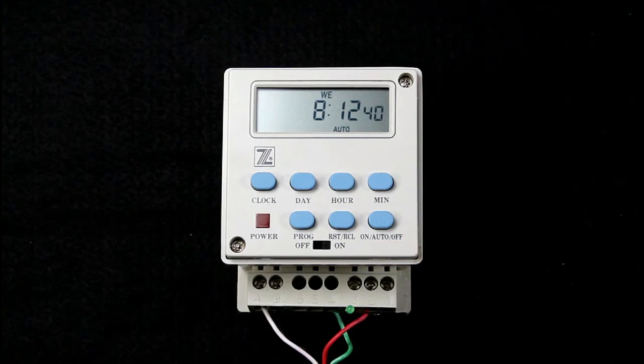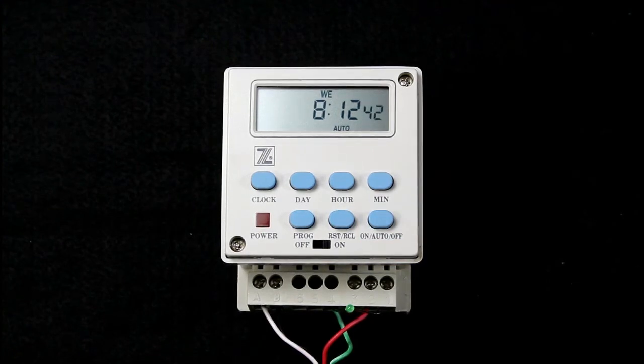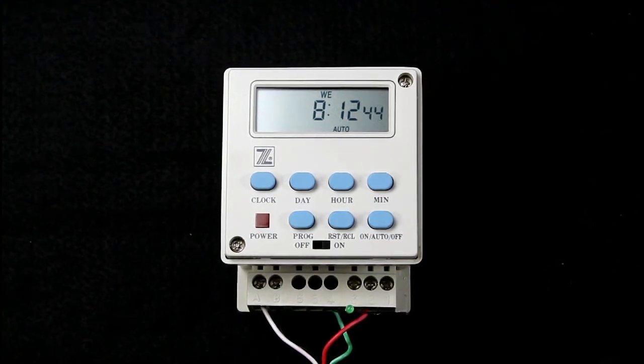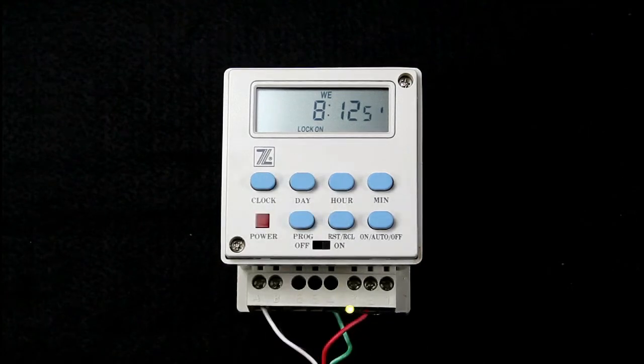In auto, the relay will cycle on and off based on the programmed cycles that have been entered into the timer. If you press the on, auto, off button and change it from auto to lock on, the relay will lock on and it will remain on indefinitely.